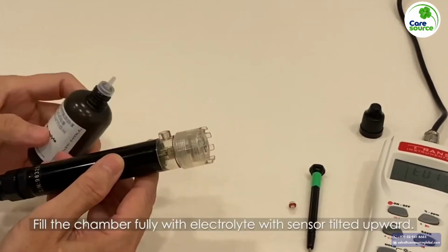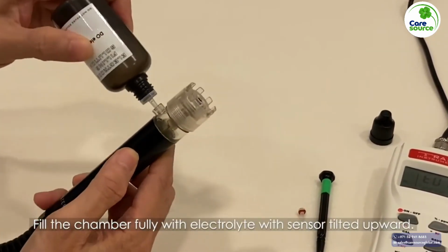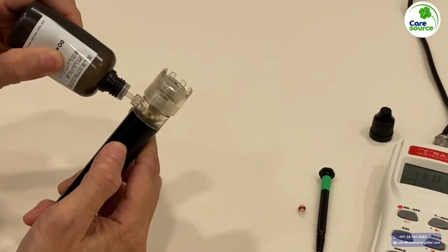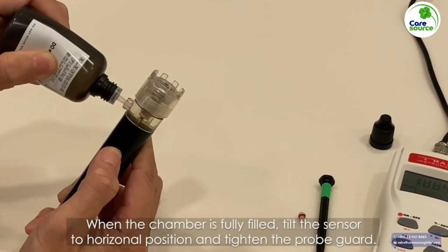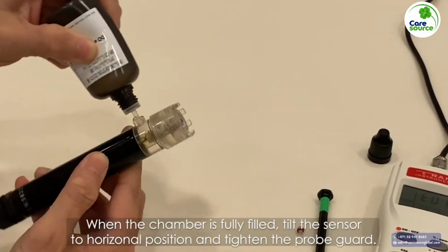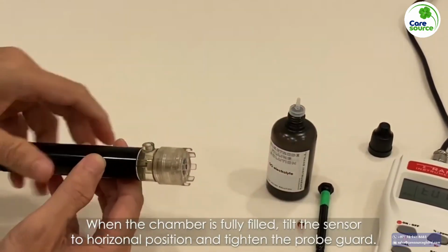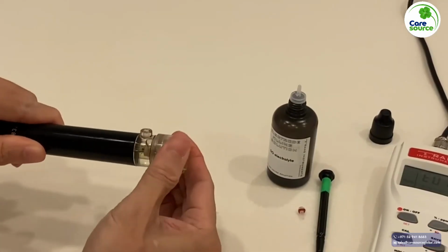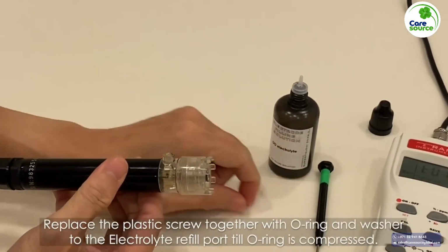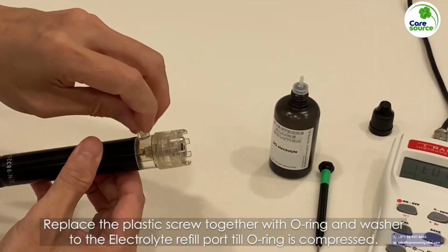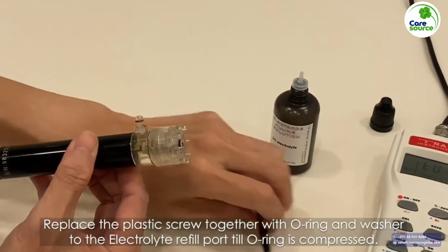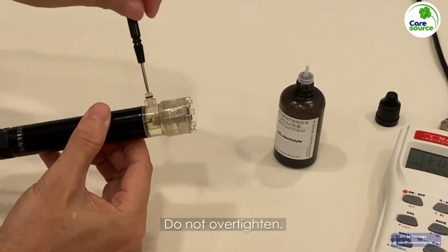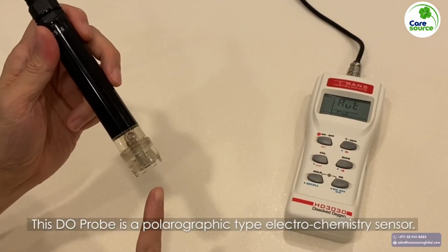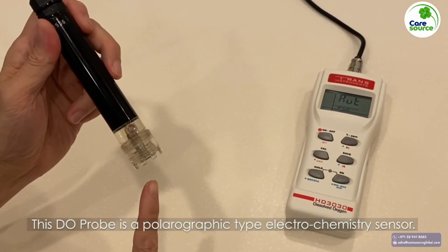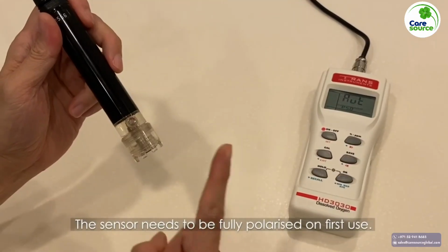Now fill the chamber fully with electrolyte with the sensor tilted upwards. When the chamber is fully filled, tilt the sensor to a horizontal position and tighten the probe guard. Replace the plastic screw together with the O-ring and washer to the electrolyte refill port till the O-ring is compressed. Do not over-tighten. This DO probe is a polarographic type electrochemistry sensor. The sensor needs to be fully polarized on first use.